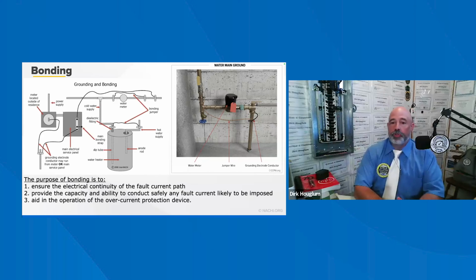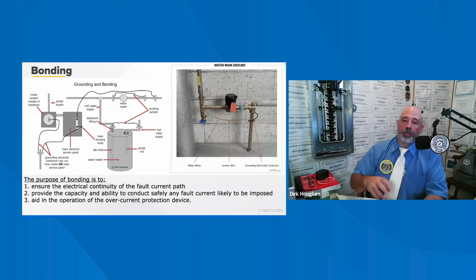Okay, I go into detail about this in the grounding and bonding video I did. To distinguish between the grounding and neutral bus bars on the panel board, the inspector can look closely at the connections to the body enclosure or the box. The panel board ground terminal bars are screwed directly into the metal body of the panel. Neutral termination bars are insulated from the panel body.